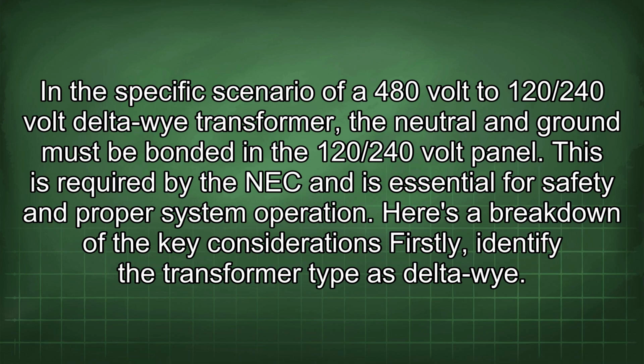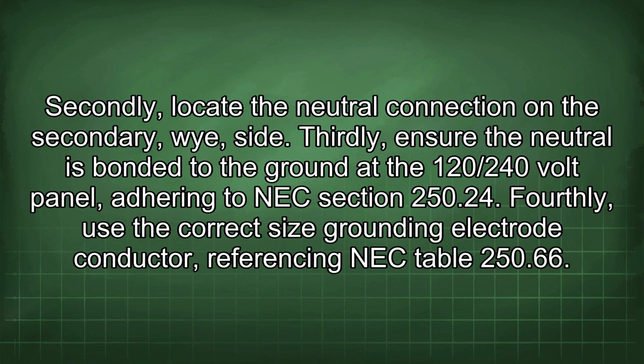Here's a breakdown of the key considerations. Firstly, identify the transformer type as delta-wye. Secondly, locate the neutral connection on the secondary Y side. Thirdly, ensure the neutral is bonded to the ground at the 120/240 volt panel, adhering to NEC section 250.24.